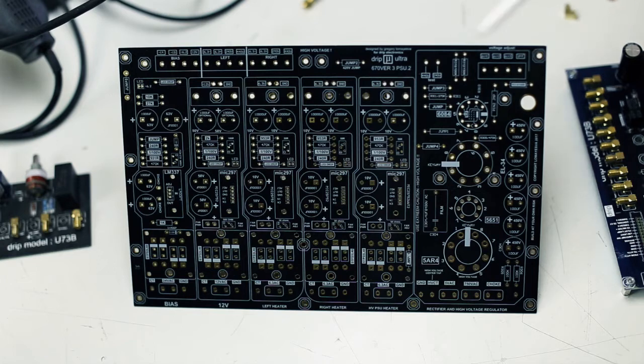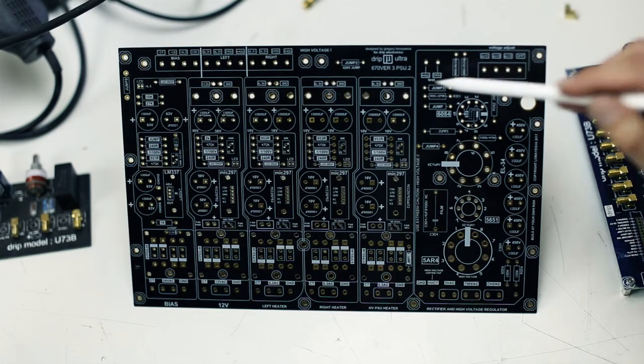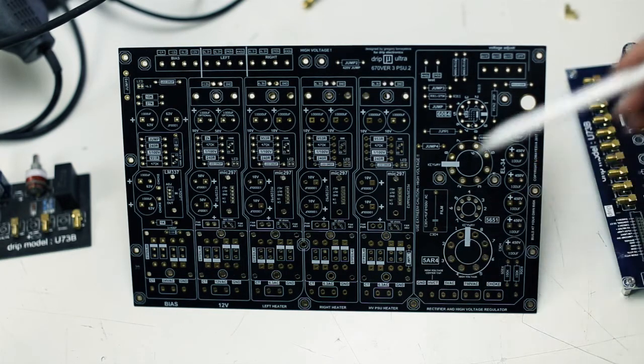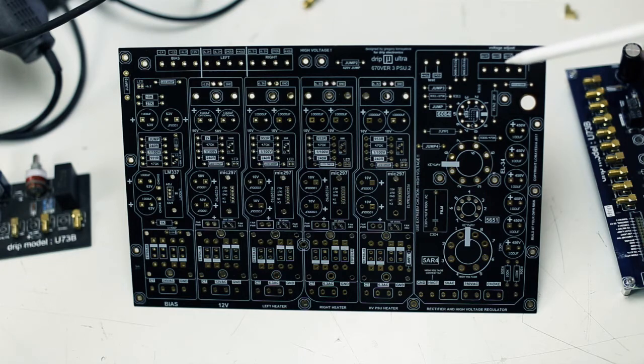The voltage adjust requires shielded wire. If you run it to the front panel, you'll need 3 conductors plus a ground wire, usually called 3 conductor plus drain or 3 conductor plus shield. There are pins for a normal potentiometer: pin 1, pin 2, pin 3, and ground is the shield.